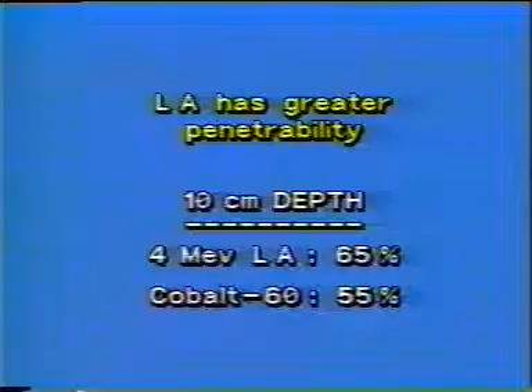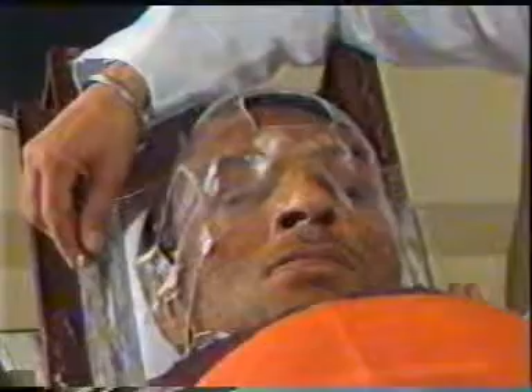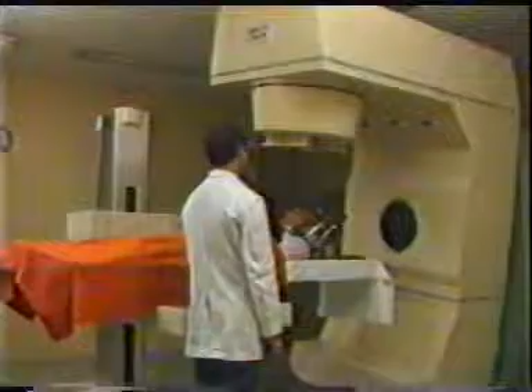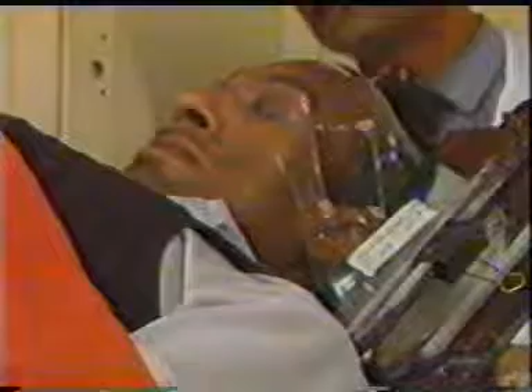Linear accelerator has greater penetrability. At 10 centimeter depth, the dose is about 10% higher than that of cobalt-60 units. Another advantage is linear accelerator has no problem of electron contamination. And linear accelerator does not house any radioactive source. So, the replacement and disposal of source as needed in cobalt units are not required for the use of linear accelerator.